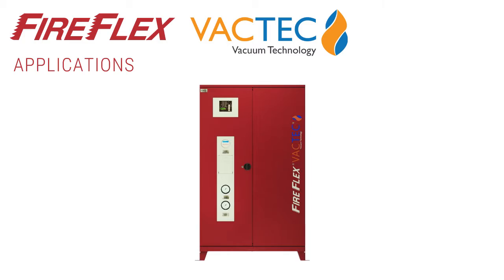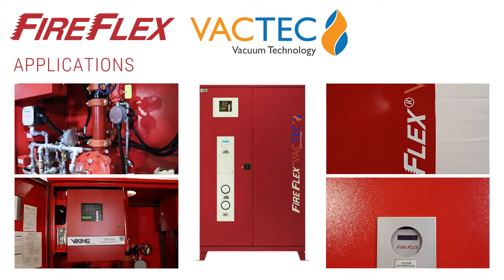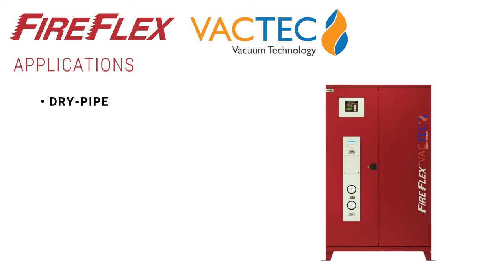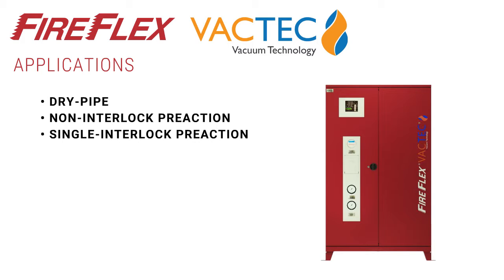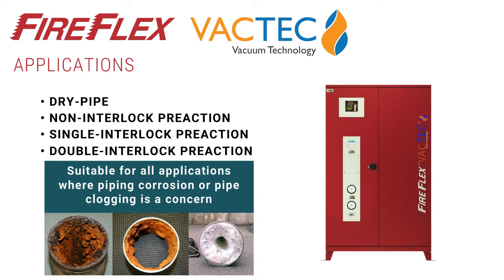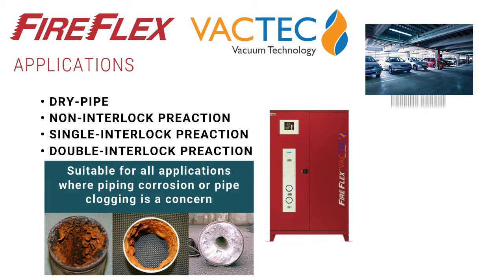Integrated vacuum fire protection systems can be used to protect all applications requiring the following types of systems: dry pipe, non-interlock pre-action, single interlock pre-action, and double interlock pre-action. The corrosion mitigation properties of the vacuum technology make this technology suitable for all applications where piping corrosion or pipe clogging is a concern. For example, large parking garages where corrosion is often a concern.